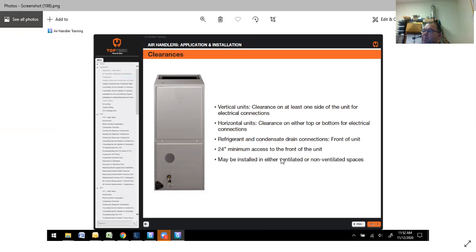You need a 24-inch minimum access to the front of the unit. That will give you plenty of access to get in there and service the unit, if you need to pull the blower wheel or blower housing to service the wheel, change the motor, or pull the coil. So don't box yourself in down the road if you have to perform service on it. This may be installed either in ventilated or non-ventilated spaces.